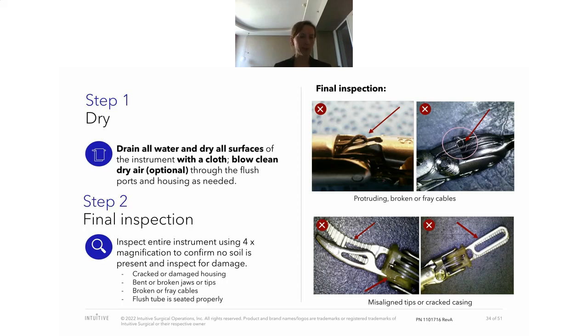We've already spoken about this on the dirty side, but also there is a final inspection step at the clean side. And here you can again see some examples of what to look out for. For example, a cable that is protruding. It's not ripped, but it certainly is not the way it should be. So this instrument should not be sterilized and sent back to the OR for use. Or on the other side, you have some frayed and ripped cables. That is also something to be aware of. Then you see some very misaligned jaws, which again should lead to the instrument being taken out of circulation and returned to us.